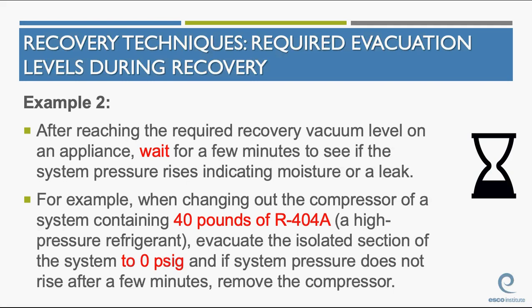Okay, after reaching the required vacuum level on an appliance, you have to wait a few minutes to see if the system pressure rises. Okay, you can't just say, cool, I'm at 10 inches of mercury, I can remove my gauges and open the appliance to the air, because there might still be refrigerant. You have to wait to see if it rises. You're doing this for two reasons. One, to see if there's a moisture or a leak, okay, and two, to make sure you don't have any more refrigerant in it. If the pressure rises, you have to start the recovery process again and get that pressure back down so it holds. If it keeps rising, there's a leak in there someplace.